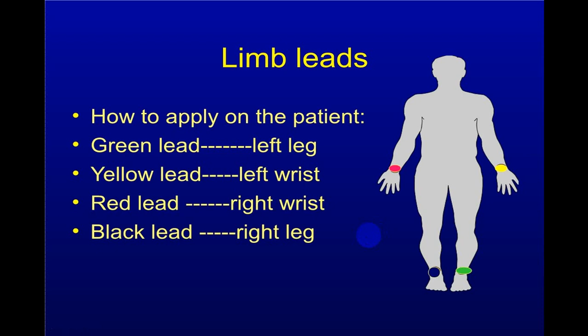So again, while taking an ECG, there should be a quiet room, the person should be well relaxed, no electrical disturbances, the room should be fully illuminated, a warm environment should be there, the person should have an empty bladder, and you should have a good ECG machine without any defects, with no break in the wire, etc. By and large, always utilize the automatic machine. Manual machines are not of good quality, so don't try to use them. You might have a single-lead recorder or multi-lead recorder, like a 3-lead or a 6-lead recorder. Either it can be with 10 cables or 5 cables, or maybe cordless. Have a proper attachment.